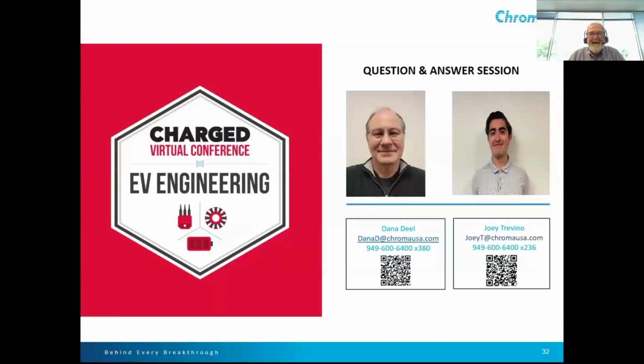Sorry about that. The next one asks if our regenerative equipment efficiency is the same when it's in regenerative mode as a source and as a load. It's only regenerative when it's actually a load, when it's pulling power from the device under test and putting it back to the grid. When it's operating as a source, it still has the same efficiency because it's only dissipating a small percentage of the input power from the grid before it sends it off to the device under test. So that efficiency is the same in both directions.